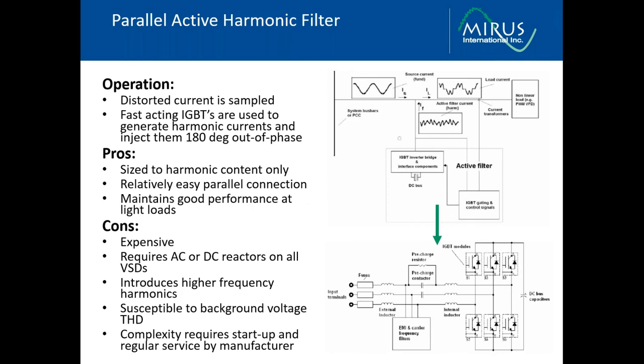In parallel active filter applications, IGBTs are used to inject harmonic currents into the power system to supply those currents required by the nonlinear loads. So we would install a CT to measure the current going into the loads. That CT would feed into the active filter, which then through, again, an IGBT or inverter section would create and inject harmonics back into the power system to supply what the load requires. And if the load is drawing its harmonic currents from the active filter, it no longer needs to draw them from the source. So you're going to see a reduction in harmonics upstream.